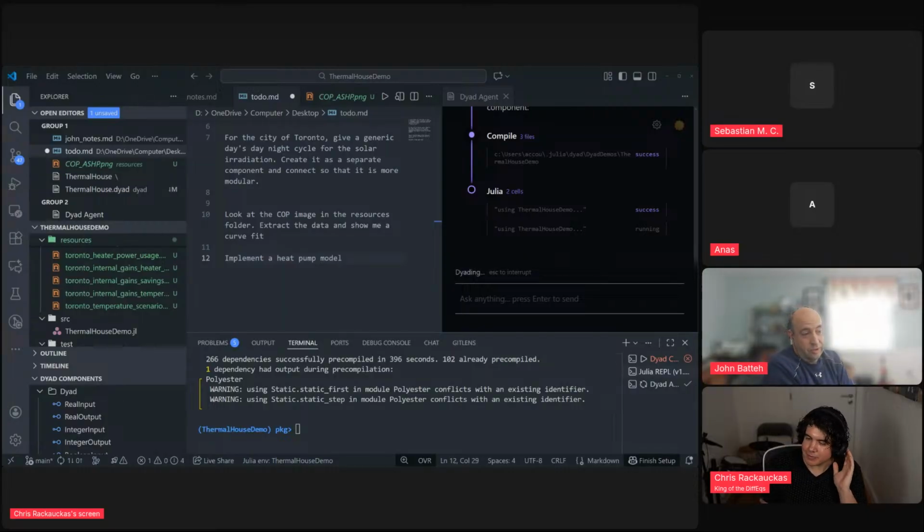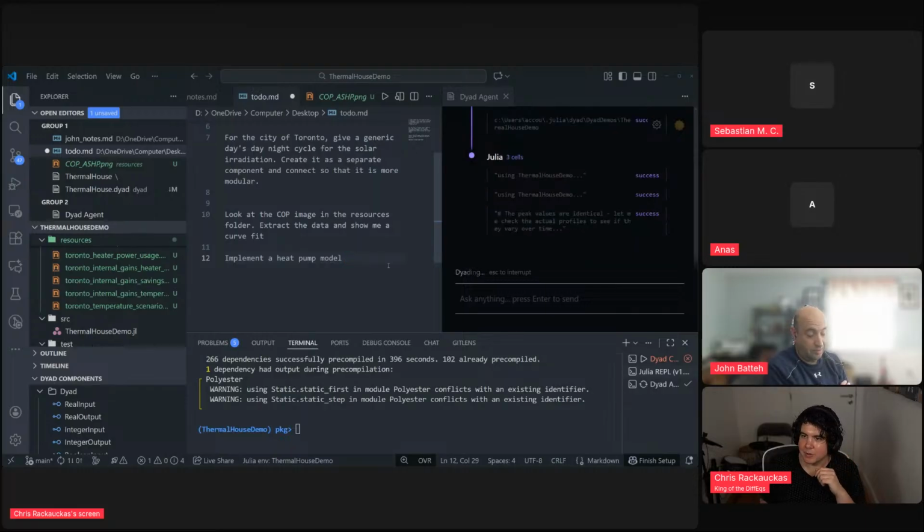Yeah. I mean, if it's too cold, it may not even be able to run at all, right? And you might have to supplement with some other method for heating. You can absolutely model that, not with what we're doing today, right? Because we're just making a performance characteristics type model. But if you do the more detailed modeling where you model the refrigerant and the components, you'll absolutely see that there would be frost. Now you have to implement models where you can grow the frost and defrost it, right? So you have to supplement your typical heat transfer models to also include the creation of the frost, the removal of the frost, the heat transfer impact of the frost.